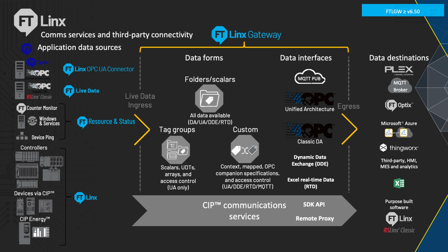The live data is the FactoryTalk Linx servers that you can define and configure within a FactoryTalk application. That's important because that FactoryTalk Linx data is not an OPC UA server. It is a proprietary connection to our Rockwell controllers. It is 10, 20 times faster than any OPC UA server you're going to get talking to a Rockwell controller. We will run circles around Kepware trying to talk to our controllers. That's all well and good, but if you bring that up in-house, not OPC UA, nothing else can use it other than Rockwell, right? So that's kind of like, okay, well, great. That's not really helping me to a large degree.